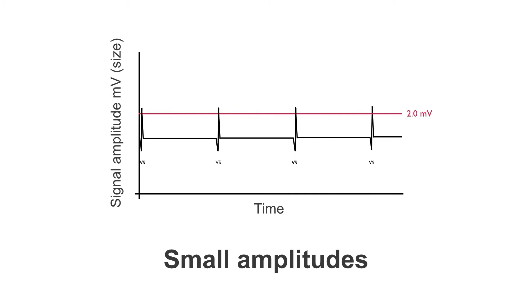The other issue of small signal amplitudes can be seen here. We have some ventricular complexes, but they're very small — they're only just over 2 millivolts, which is where our ventricular channel's sensitivity is set to.